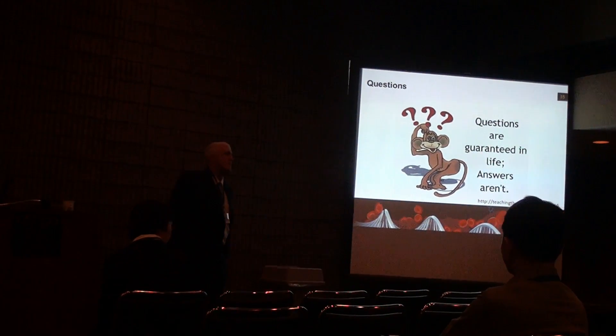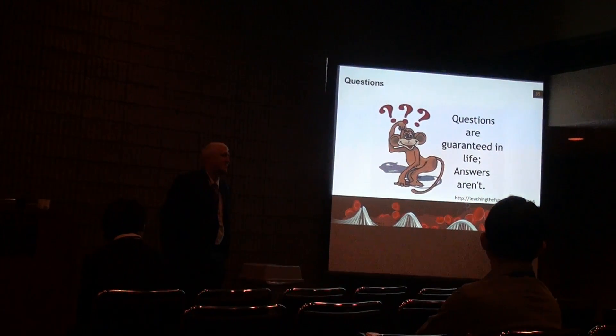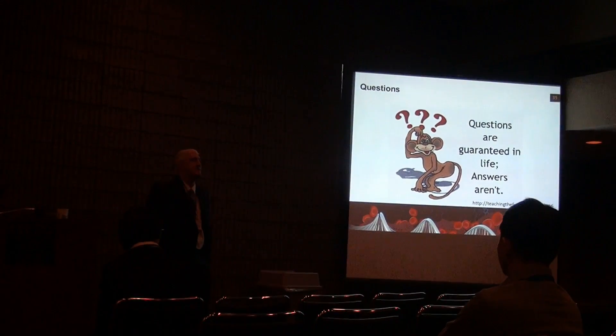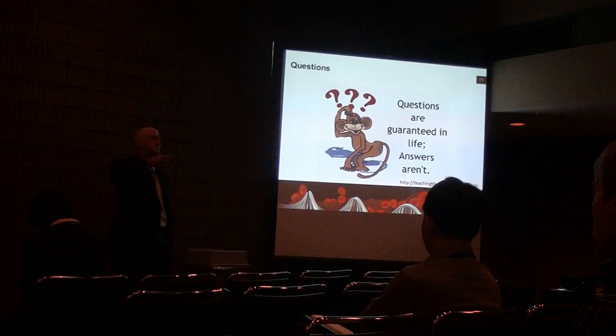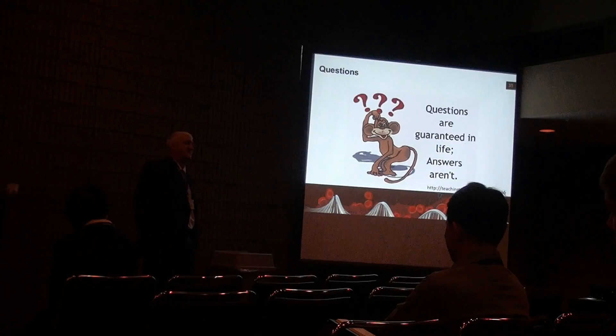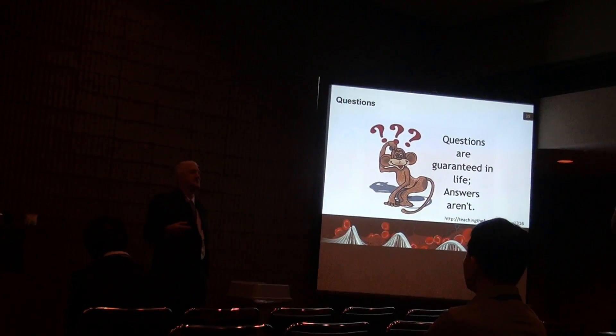Q: Very impressive. Have you gotten any more data from the irritation of the eye? A: Yes. We actually have data on every single animal multiple times a day, repeated use, as well as a longitudinal study going over a 12-month period of continual use. Basically, if you had a type 1 diabetic who was really good about monitoring their diabetes, we have enough data to show it's safe. As for version 4.2, we're doing a material changeover as well, so we're definitely going back to a preclinical study — if we change the material, it has to be tested on an animal again.